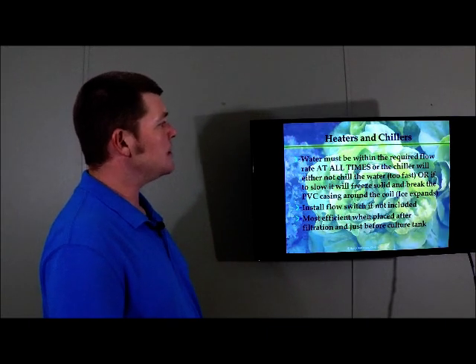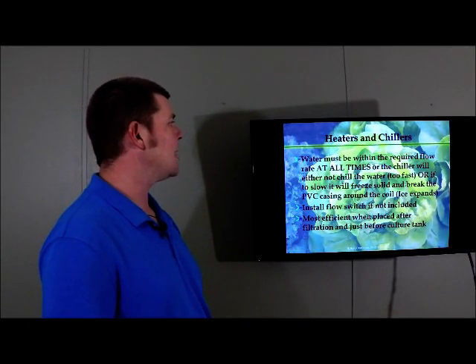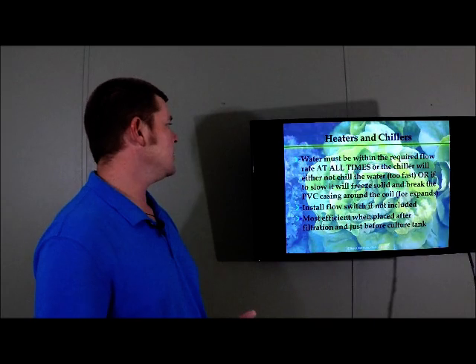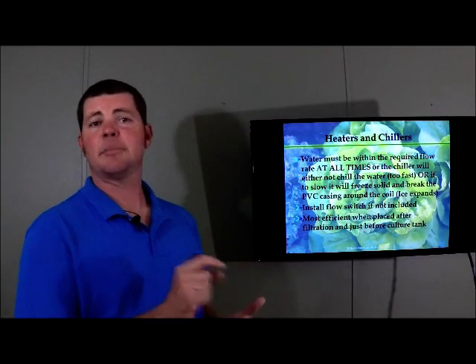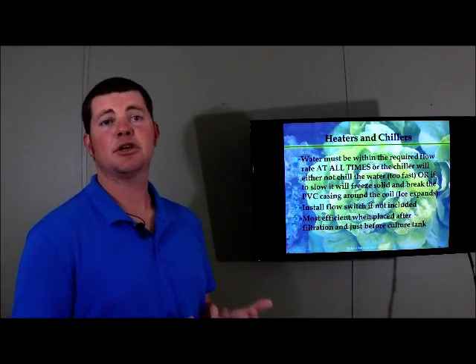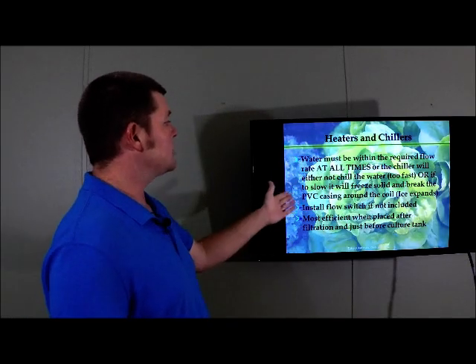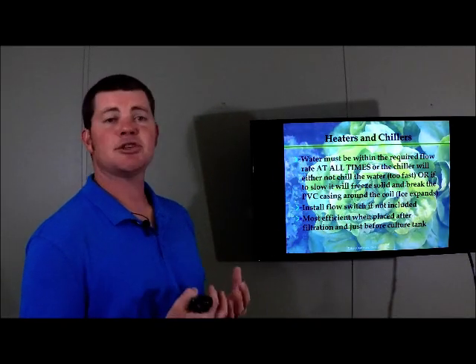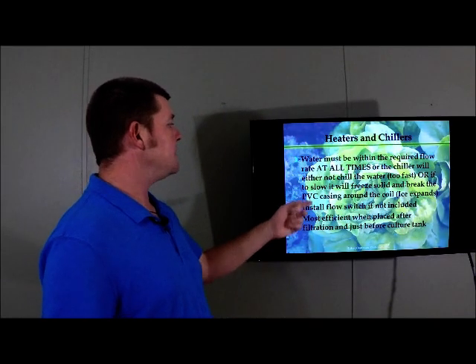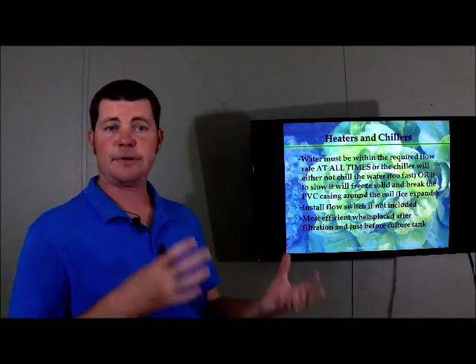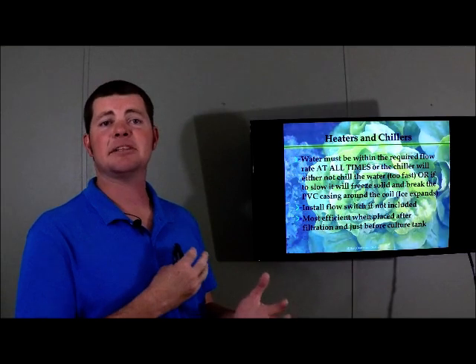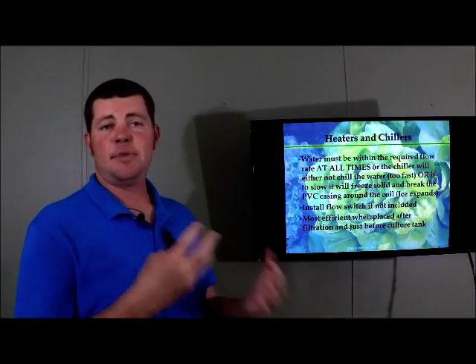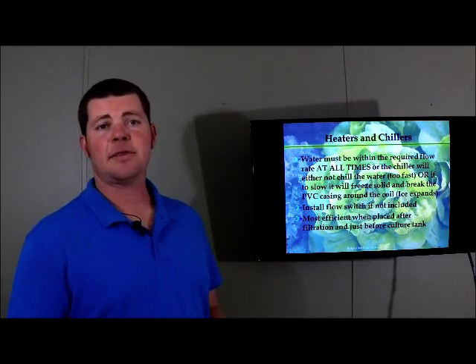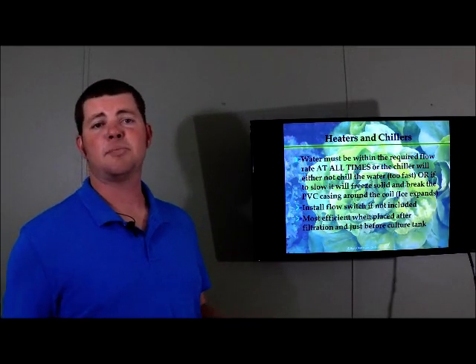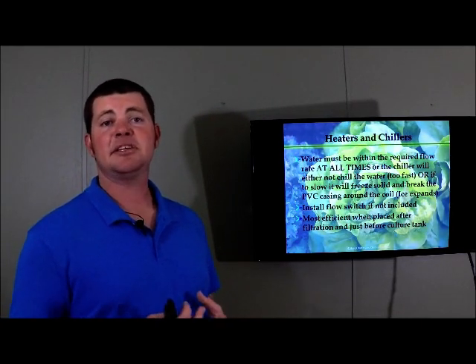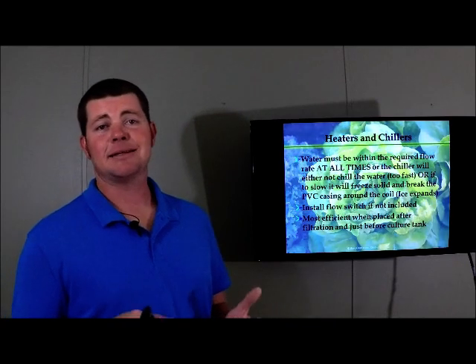Water must be within the required flow rate of the chiller at all times, or it will either not chill the water. If the water is going by the coil too fast, it's not going to chill it properly, or if it's going too slow, it'll actually freeze solid and break the PVC casing around the coil. So it freezes up, ice expands, and it cracks the PVC case. You finally shut it off, let it thaw out, plug it back in, and water comes pouring out of the unit because the whole PVC shell is broken. And guess what? That's not repairable.